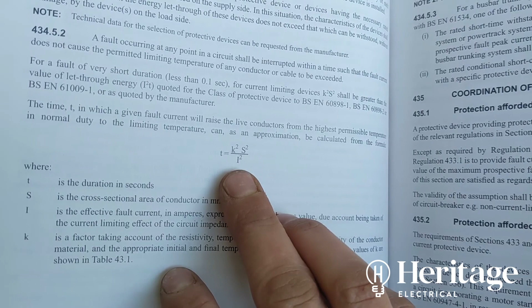So the actual individual circuits, you know, these are good for give or take about 80 amps maybe. I need to just go in the good book to get an exact value for that, but they're good for about 80 amps. The two circuits that we're going to be having are not going to be pulling anywhere near that, so that's fine. So you know, the cable is not going to be overloaded. I just wanted to check if there is a fault upstream from this board. So in other words, between the tail blocks and here, which is literally 1 brick's distance through there, so it's not even 2 meters. But just, yeah, belt and braces, make sure that that cable is protected if there is a fault between the tail blocks and here.